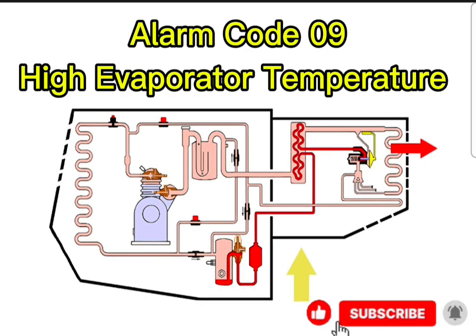The system literally traps its own thermal exhaust and suffocates itself. Exactly. And that also perfectly explains the final physical culprit the manual lists, the evaporator fan failing. Yep. Even if the valves and doors work perfectly, if the fan motor dies and isn't physically moving the air across the coils to dissipate the energy, the heat just pools in a stagnant pocket until the ungraded sensor screams and shuts the whole operation down. It's a very logical, physical progression of troubleshooting. You check the pipes, you check the doors, you check the fans, tangible parts breaking in tangible ways.